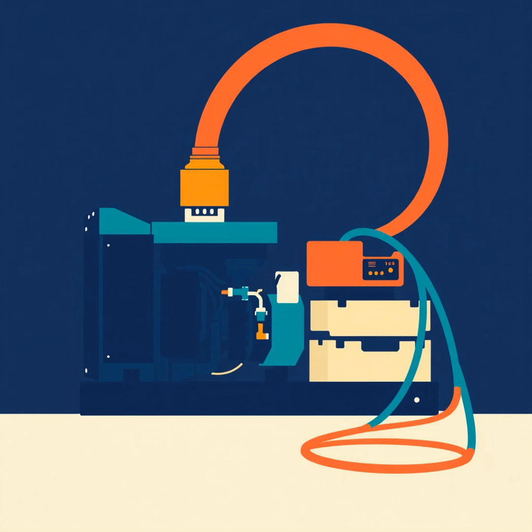Not necessarily. Every time you add a redundant component, you are adding complexity. You are adding more wires, more sensors, and more software to manage the failover. If the transfer switch, the system that is supposed to switch from the main power to the backup power, fails, it does not matter how good your generator is. You have created a new single point of failure.